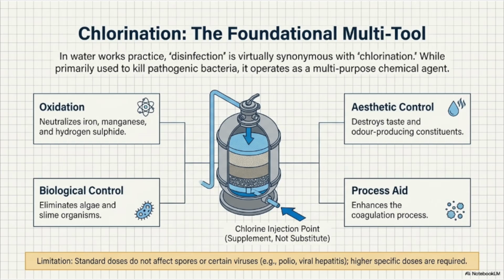It performs oxidation, neutralizing iron, manganese, and hydrogen sulfide. It performs biological control, eliminating algae and slime organisms. It acts as an aesthetic control agent, destroying taste and odor producing constituents, and it also acts as a process aid, enhancing the coagulation process.